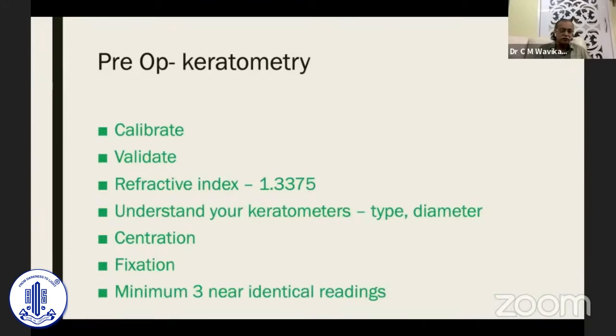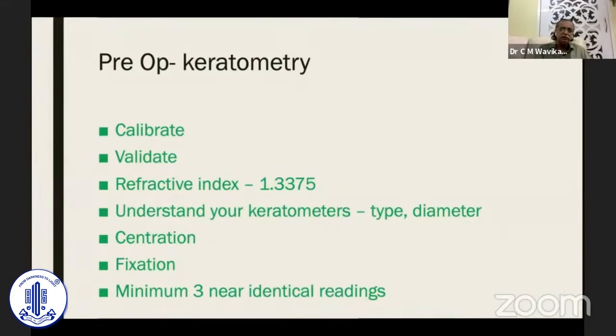That is not all — we need to know more about keratometry. First, calibrate and validate: you must calibrate every day and whenever there is a change of user, otherwise the readings have no meaning. You should know what kind of keratometer you are using — the refractive index and the diameter on which it gives the K reading. Centration and fixation are very important for getting correct readings, and you must try for three nearly identical readings so that they are predictable and reproducible.